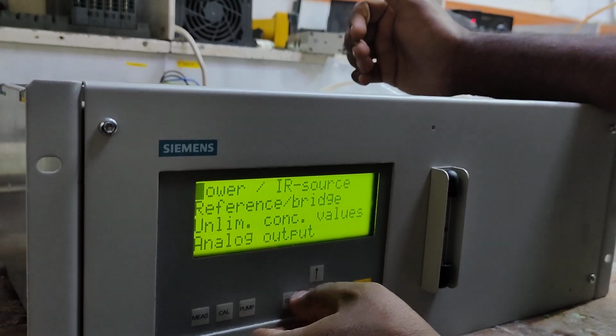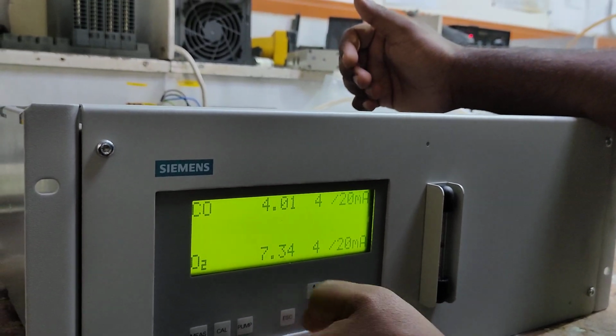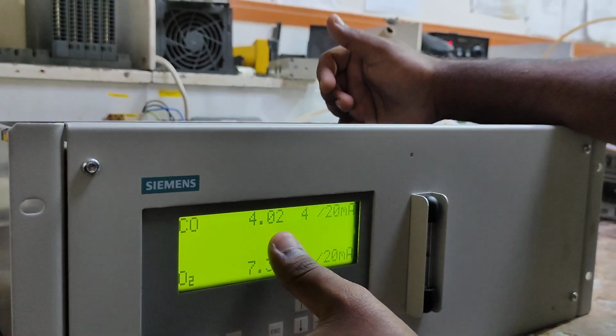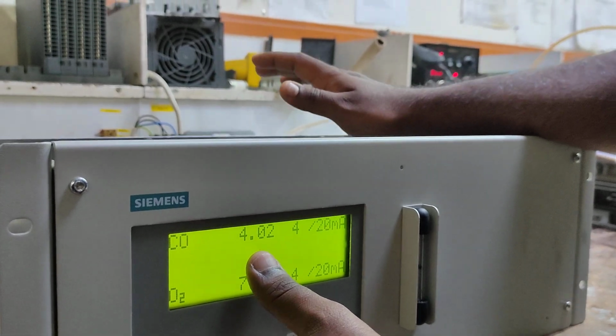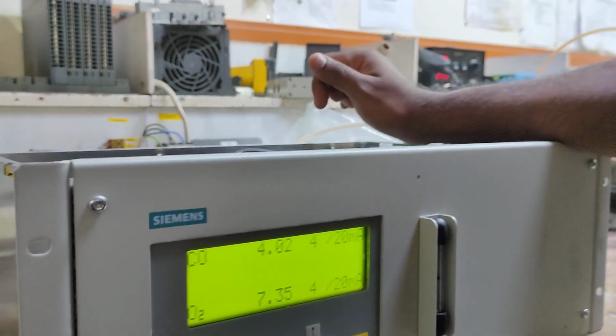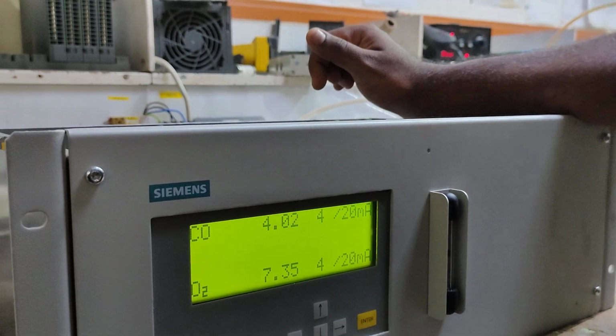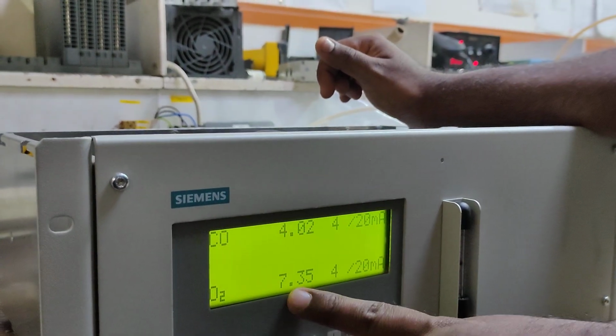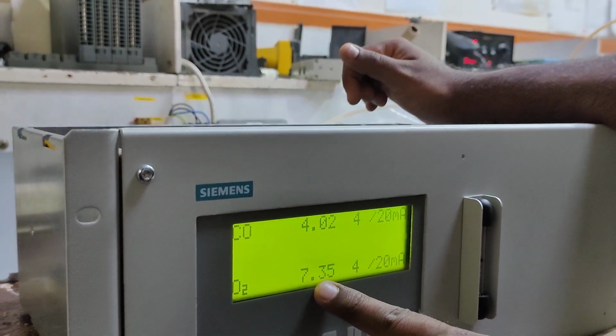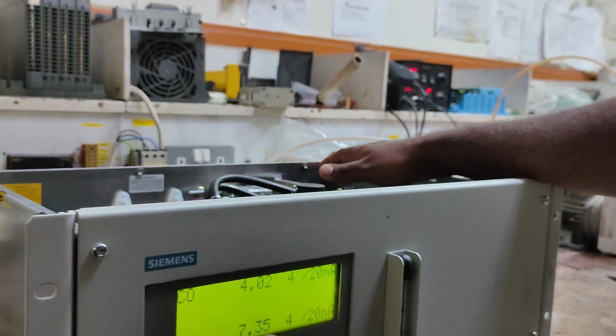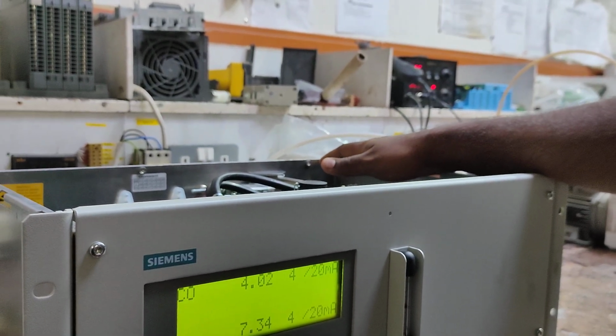The other parameter now is the analog output. It shows how much analog output it is giving in the loop. If you want to verify the range at the DCS, you can see how much the output is. It is 4 milliampere and 7.35 for O2. Why are they giving that? What is the range of O2? We can see now.